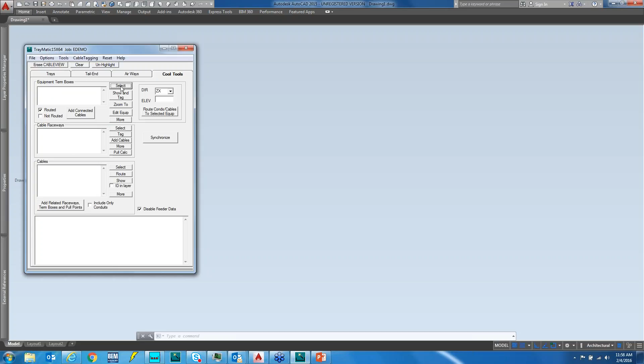In the case of a motor control center, the cables are just going to drop from the motor control center straight into the tray without necessarily going through a physical conduit. So in this case, I want to be able to field route these because I don't want it to be restricted by a conduit size.